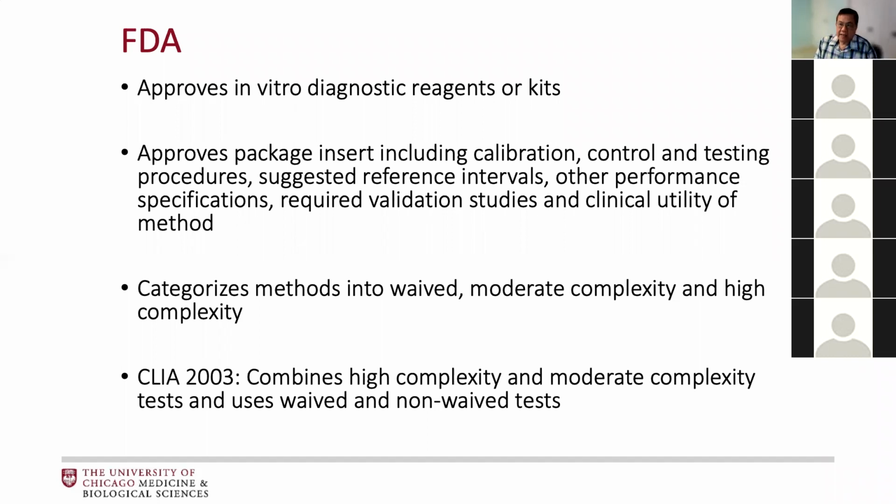And even if you buy an FDA approved test out of the box, it is your role as a lab director to make sure that you do validation studies to verify that the performance of the test as specified in the package insert is met before you launch it for your hospital. We do this as a matter of fact, and some of your colleagues or classmates who have already done chemistry can tell you that. If you talk to Clarence, he does this all the time, spending his time in chemistry doing verification and validation studies, most recently for the COVID antibody test.